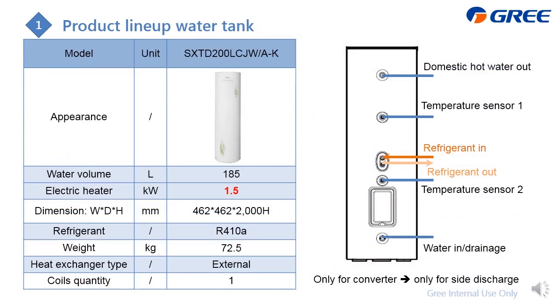For the water tank, you can source it yourself. If you choose from Gree, here is the model we can provide, and it is 185 liter with a built-in e-heater of 1.5 kilowatt. And here is the dimension, and you can find that it is 2 meters high. And here is the weight, and inside it applies refrigerant R410a. And here is the most important point: this is the external coil, which means it can only be used for the converter, which is only for the side discharge.